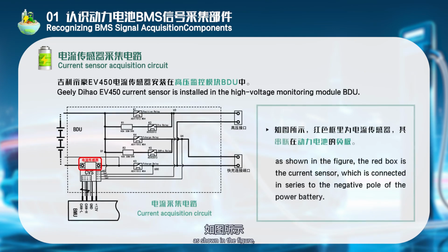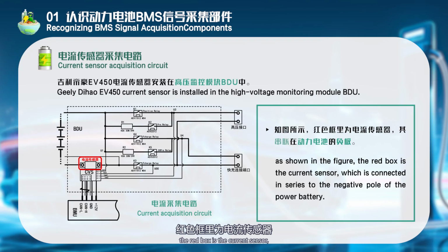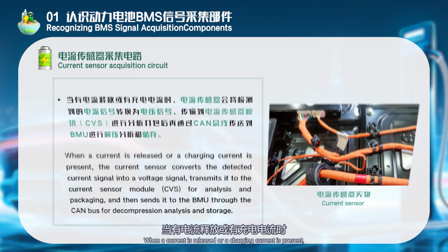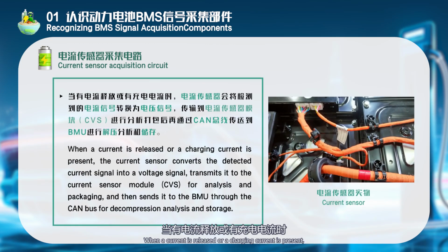As shown in the figure, the red box is the current sensor, which is connected in series to the negative pole of the power battery. When a current is released or a charging current is present, the current sensor converts the detected current signal into a voltage signal, transmits it to the current sensor module CVS for analysis and packaging, and then sends it to the BMU through the CAN bus for decompression analysis and storage.